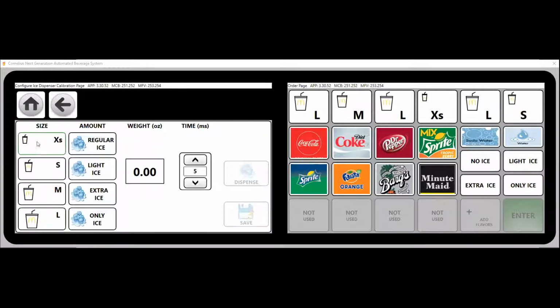Ice dispense calibration. This is where you have all your cup sizes. You have your portions of ice here on the right, and you have an up and down arrow, intended for you to either increase or decrease time to adjust your portion of ice. So for example, start off with child, regular ice. If you need to increase or decrease your portion, let's say we want to bring it down to 65, I do a dispense, and I put my child size cup underneath my ice chute assembly. I get my sample reading. If my sample reading is still low, I'll increase my time. Let's say 70. 70 is the number that gives us the correct regular ice portion that we need. At this moment, you press save.